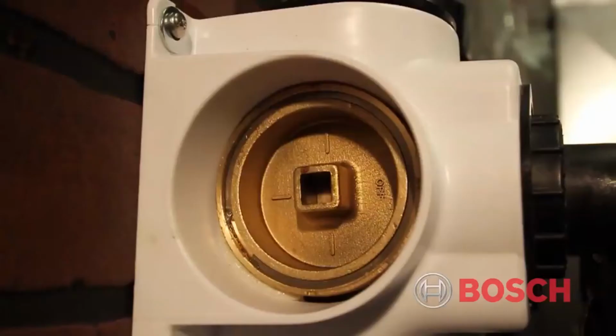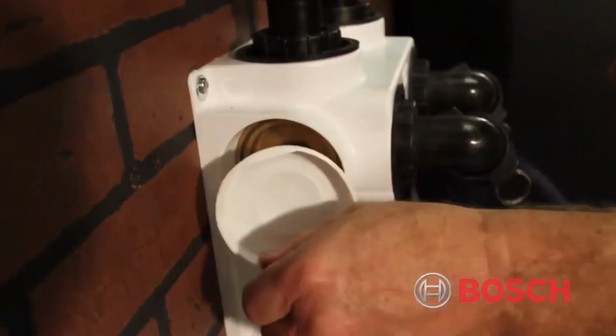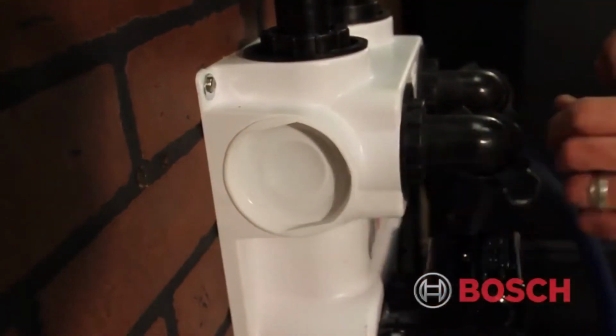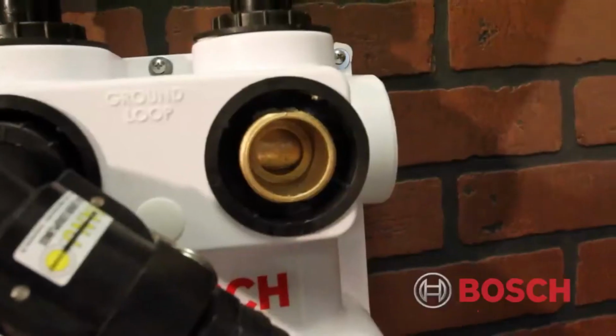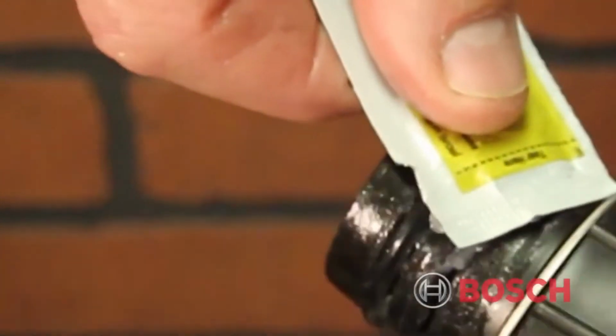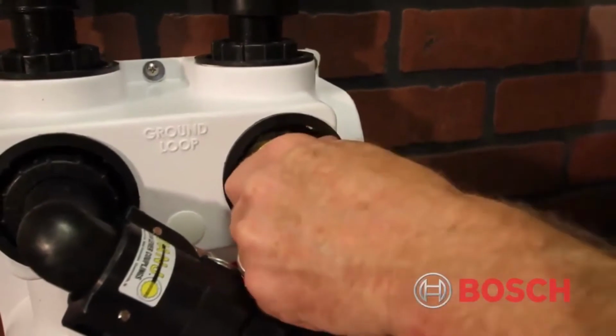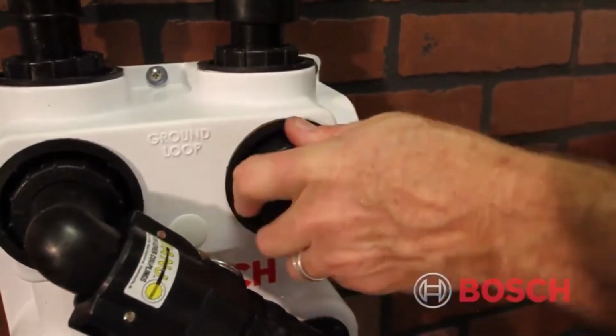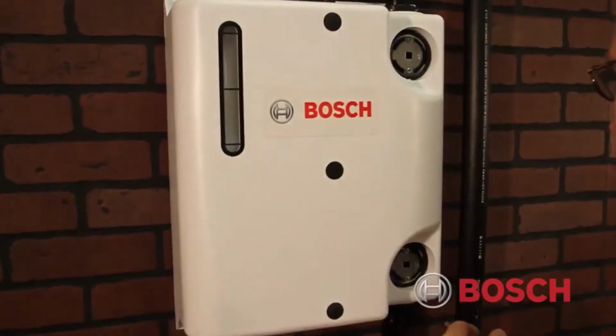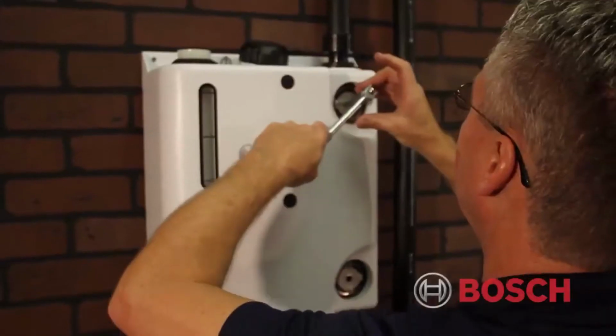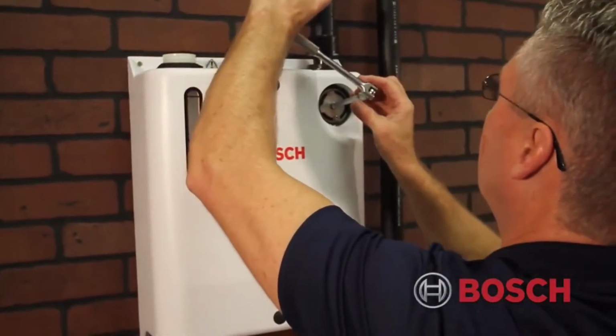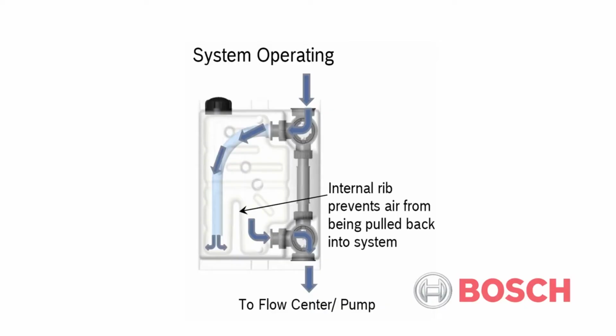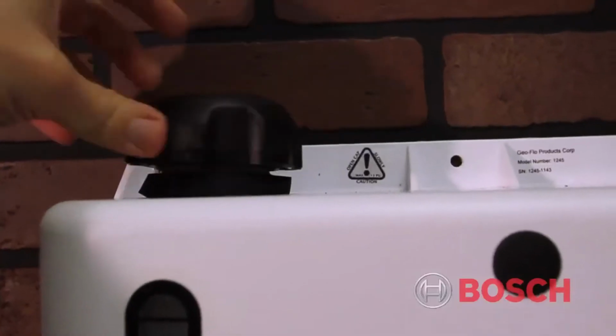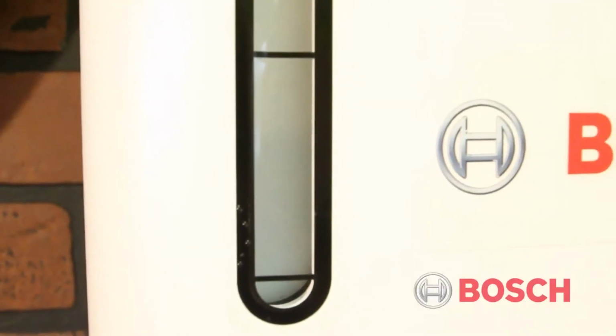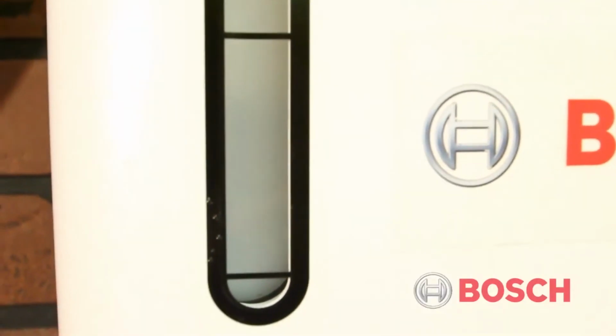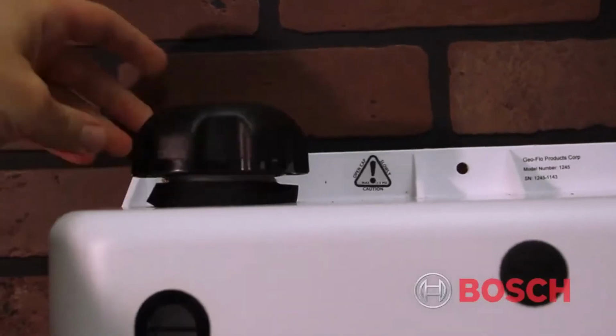At this point, we're finished with the flow center 3-way valves and we can reinstall the plugs and protective caps. Remove hoses and flush cart connectors from the flow center. Apply white petroleum jelly to both double O-ring flow center plugs, insert the plugs, and screw on the caps. Next, we're going to fill the Geoprime 2.5 gallon reservoir. Rotate the Geoprime tank 3-way valves to the operation position. To fill, simply remove the reservoir cap and add water. Using the sight gauge, fill up to the halfway mark and then replace the cap until it clicks.